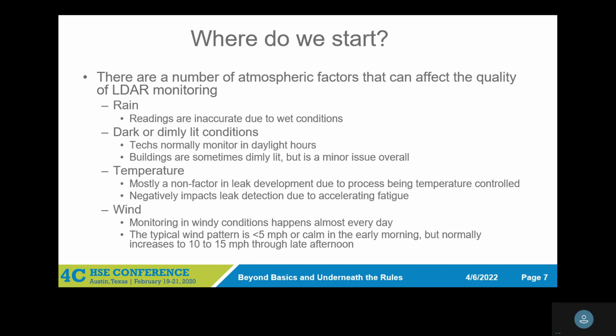So the temperature, I'd like to walk that back. Especially around the bullet tanks, when those bullet tanks get cold and frozen at 15, 20 degrees, the pressure underneath those tanks goes from, in normal conditions around 80 degrees, probably around 140 pounds, 90 degrees, maybe 150 or something like that. When I did my study, that's about where I compared it, 80 to 90 degrees, and I didn't really see any difference in the leak rates.